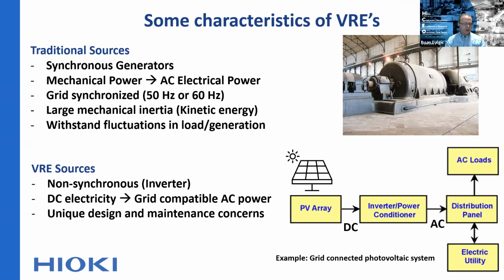Now, with VRE sources, they're non-synchronous. They depend on power electronics, an inverter or power conditioner, to convert the generated electricity into the correct voltage and frequency of the grid and to synchronize it with the grid. So VRE interfaces to the grid using power electronics—the power source is not directly coupled to the grid dynamics, so there's no mechanical inertia capable of reducing fluctuations.